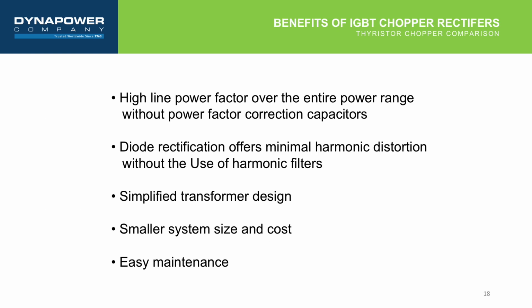In conclusion, chopper rectifiers offer several operational benefits over conventional Thyristor rectification. These include high line power factor over the entire power range without power factor correction capacitors. Diode rectification offers minimal harmonic distortion without the use of harmonic filters. Simplified transformer design eliminates needs for saturatable reactors and interface transformers, as current sharing and regulation is achieved by means of electronic chopper control. Elimination of space requirements for the line power factor and harmonic line filters leads to reduction in overall system size and cost as well.